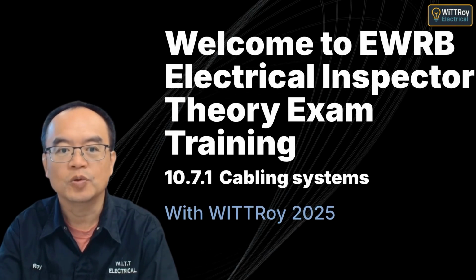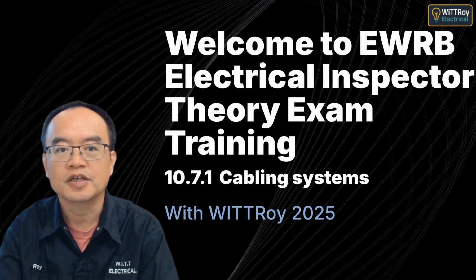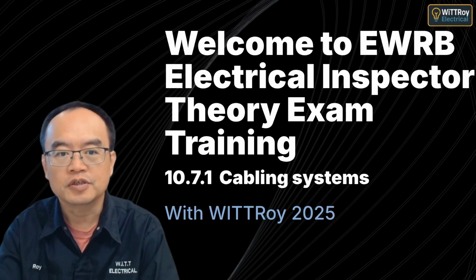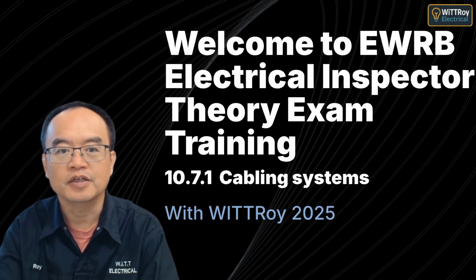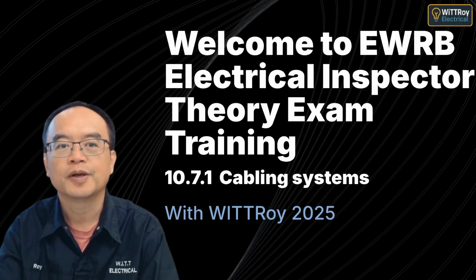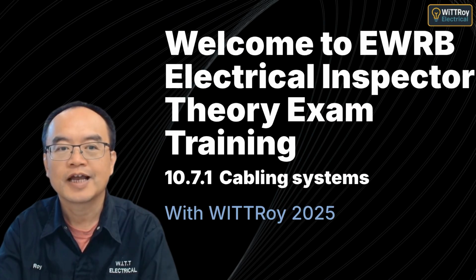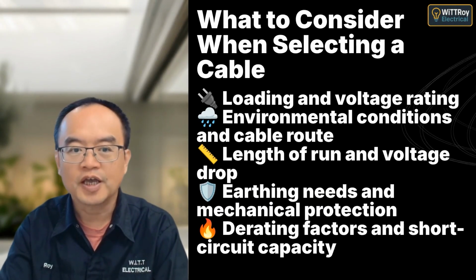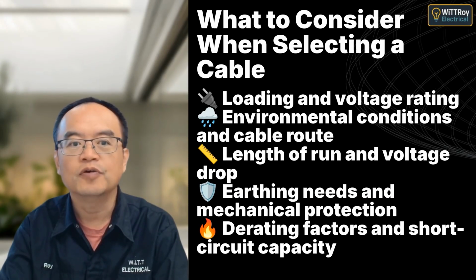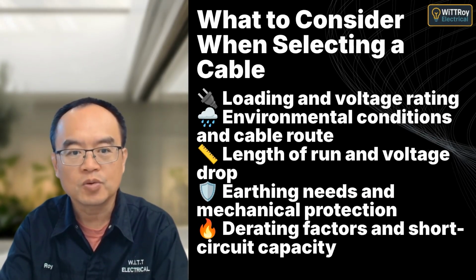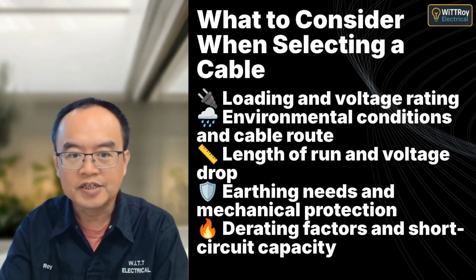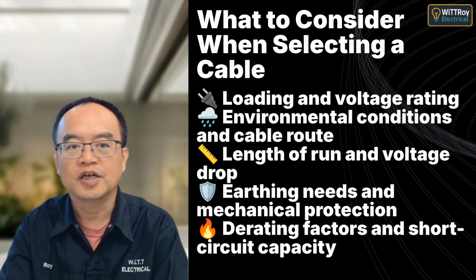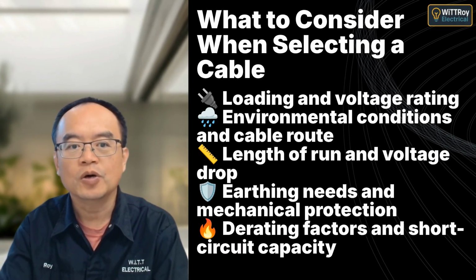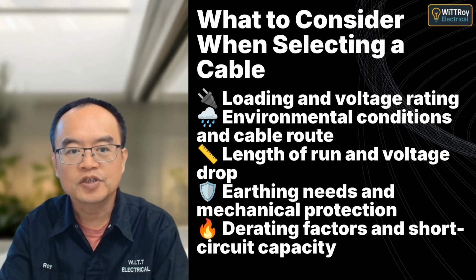In this short lesson, we're looking at cabling systems, how to select the right cable for different situations, what factors must be considered, and how to apply the correct tables from AS/NZS 3000 and AS/NZS 3008. When choosing a cable, you must consider the load current, voltage rating, installation environment, run length, mechanical strength, and any derating factors. Short circuit current levels and earthing requirements are also key. This ensures safety and reliability.